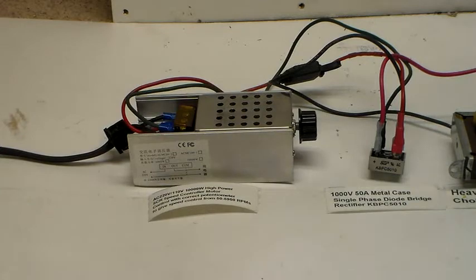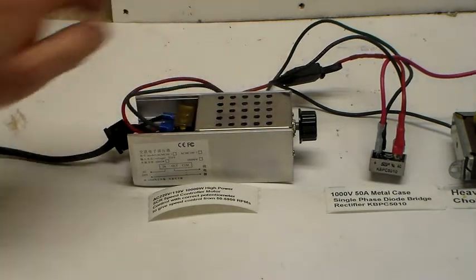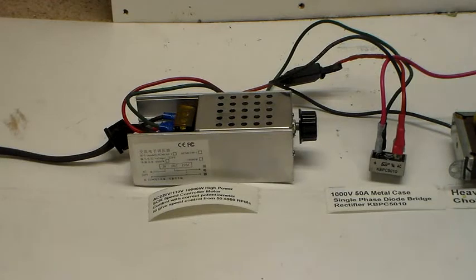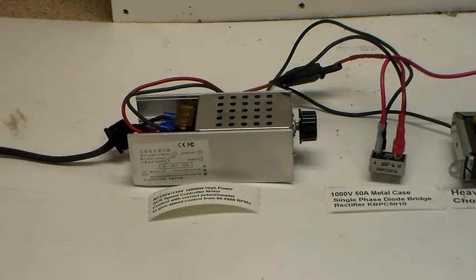And in line you can't see it, but there's a 35 amp fuse holder, which right now has a 25 amp fuse in it because the maximum draw of the motor is 17 amps.